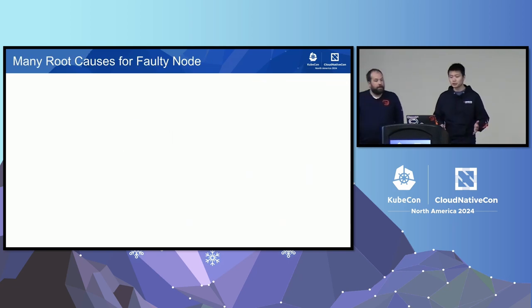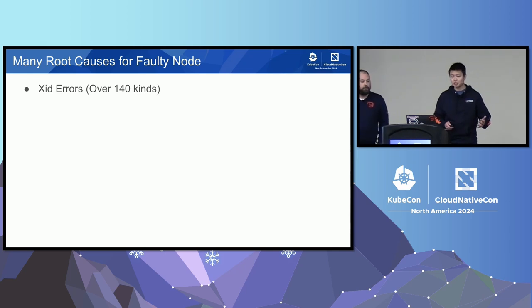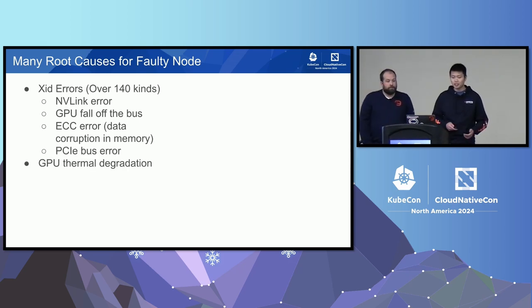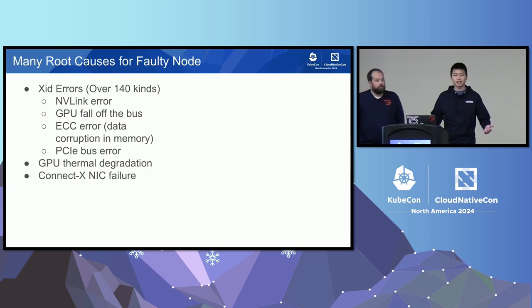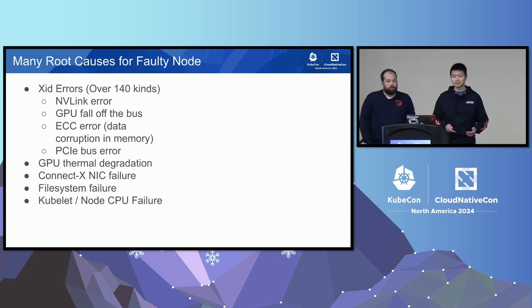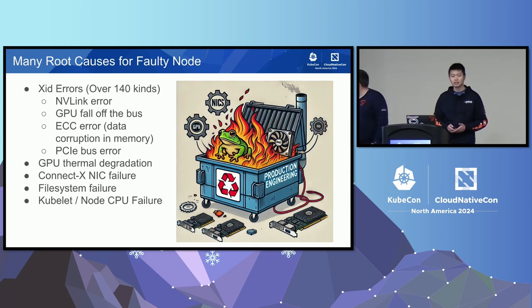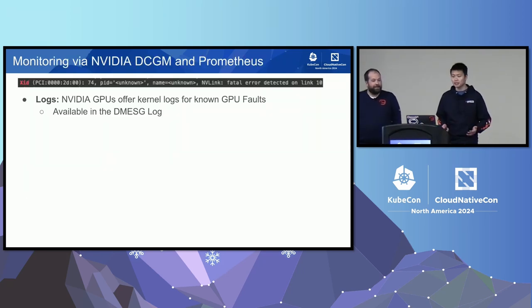A small number of node failures can disproportionately affect a large run. There's a variety of failures — some are GPU errors that manifest as XID codes, and there are over 140 different kinds. The most common are NVLink errors — the high-speed interconnect between GPUs — GPU fall-off-the-bus errors where the GPU is disconnected from the PCIe bus, ECC memory errors indicating data corruption, thermal degradation from overheating, ConnectX NIC errors, file system failures, kubelet hung issues, and CPU out-of-memory. These all contribute to very heavy on-calls for production engineers, so we need precise monitoring to gain real-time insights into GPU health and performance.